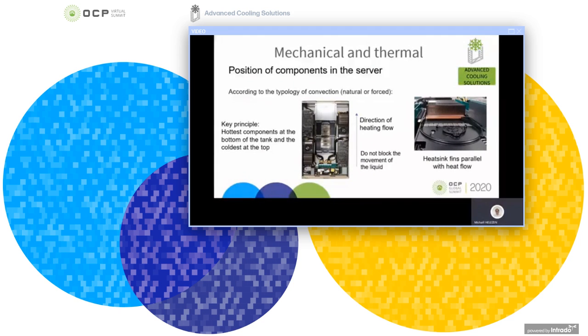The component will be placed to avoid blocking the flow of the liquid and potential hotspots. To do so, the exchanger fins will be oriented into the direction of flow, as shown in these pictures. It is also possible to size the fins according to the type of the liquid used. The aim will be to optimize the heat exchange. The thermal capacities of this type of cooling make it possible to imagine arrangement of components and densification previously impossible with air.